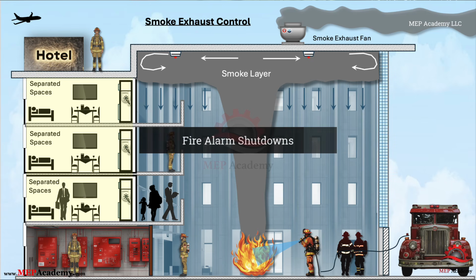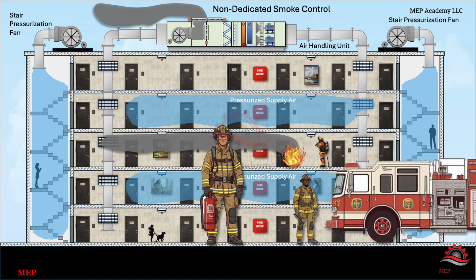The fifth issue involves fire alarm shutdown interfaces and system interlocks. Many HVAC systems are required to stop, start, or change operating mode in response to fire alarm signals. Mechanical drawings may indicate shutdown intent, while fire alarm drawings identify monitoring points, but the exact wiring responsibility is not always shown. The result is a system where equipment is installed and powered, but the required operational response does not occur when tested. This is typically discovered during functional testing or commissioning, when systems are required to operate together for the first time. The coordination challenge is determining who provides the relay, who runs the wiring to the equipment, and who verifies proper operation during testing. Without clear assignment, each trade may complete its individual scope while the overall system remains incomplete.